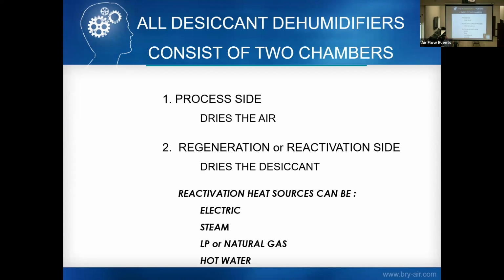For reactivation, we use electric, steam, LP, natural gas, or hot water on projects that don't require as much dehumidification, or we use hot water also as a booster heat. Sometimes to save energy, we'll put in a hot water heater if they have a boiler readily available to preheat the air, so we use less reactivation.